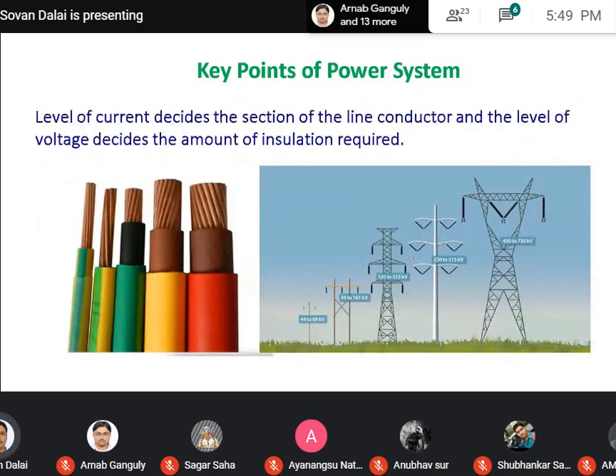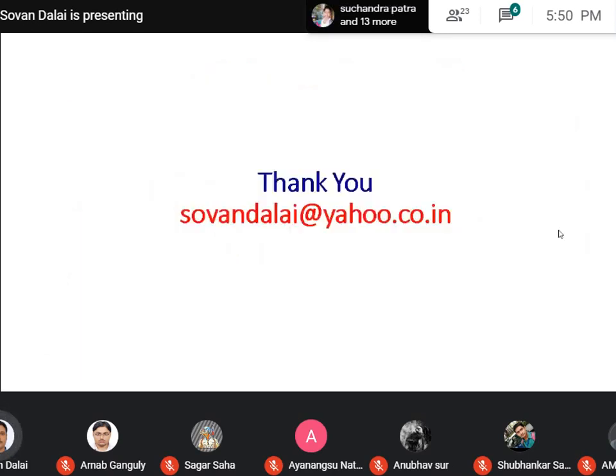So the level of current decides the section of the line conductor. If the current rating increases, the cross section of the conductor gradually increases. So conductor cross section depends on the current, but the voltage level depends on the insulation level. Gradually, from this side to this side, the voltage level increases, so the tower height also increases, because the air column basically acts as an insulator. If you consider 735 kilovolt compared to 220 or 230 kilovolt lines, a higher air column will be required, because the air column height is the deciding factor for the air insulation. Okay, thank you.